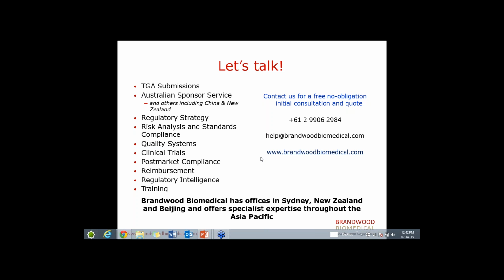It's slightly different with Class 3s because they have an additional requirement to have a design examination certificate for some Class 3 devices. In that case, if there is a significant change to the product, you will need to do a device variation application. Again, it's like the device application. You've got your certificate already issued by the notified body, so the process is supposed to be quicker. It's usually quicker.